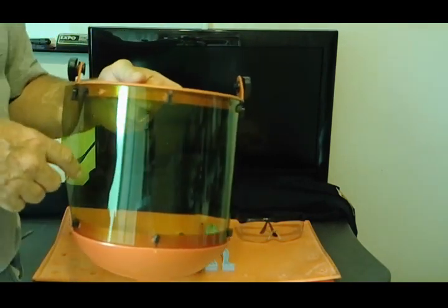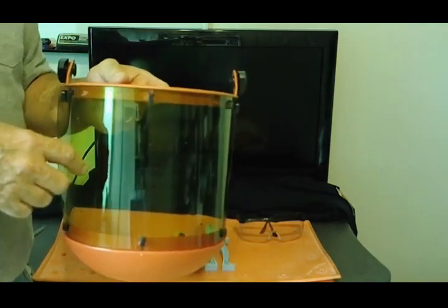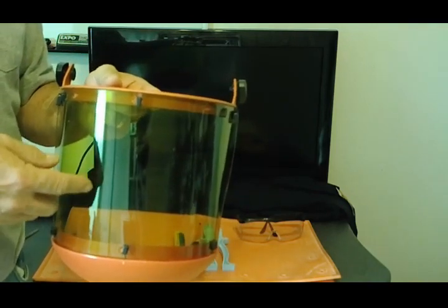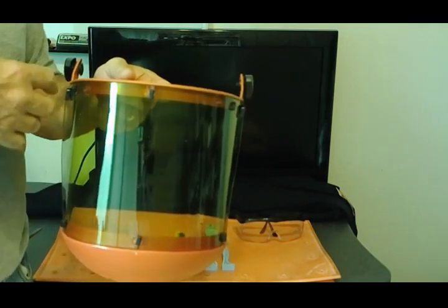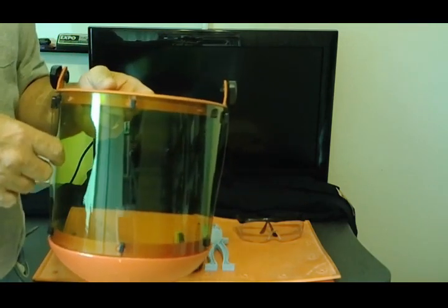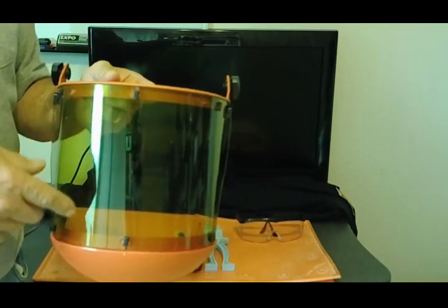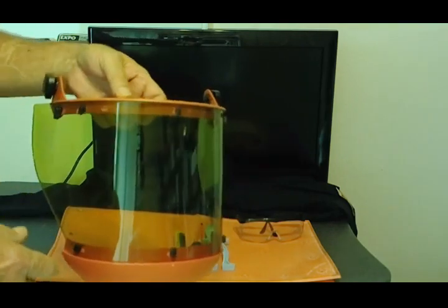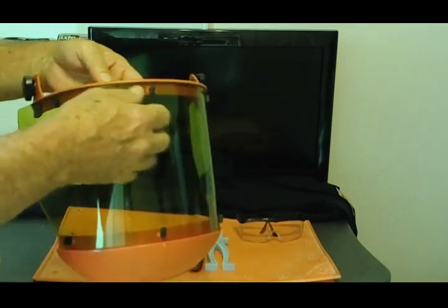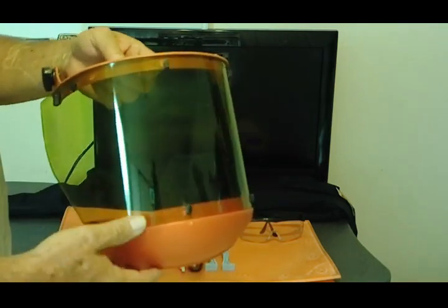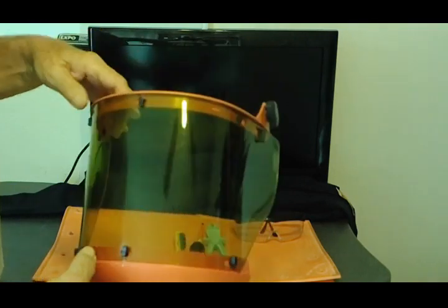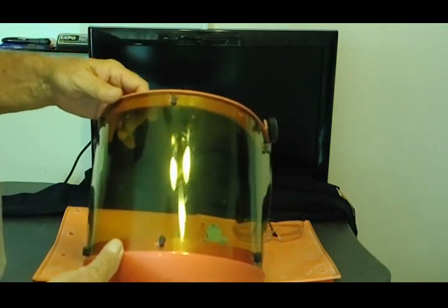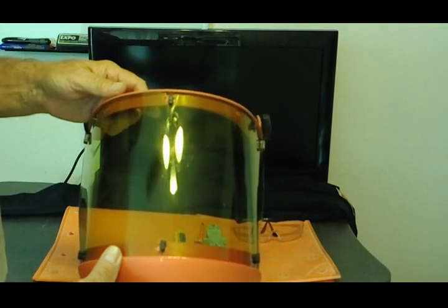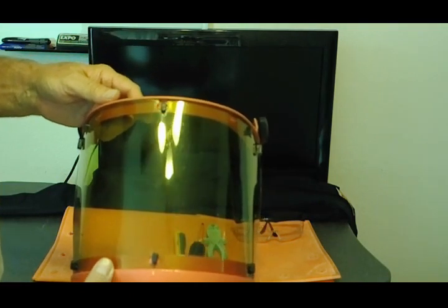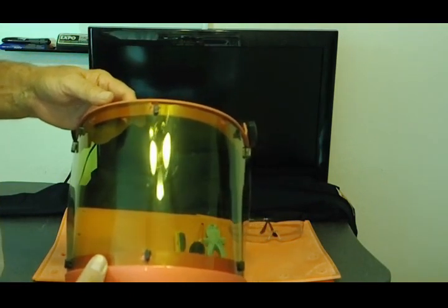Now the yellow tint, it can be a green tint or yellow tint. That yellow or green tint is there to provide UV protection in the event of an arc flash. Now they do make a clear one, but if there's ever an arc flash, you're going to have a real case of welding burn or sunburn right there on your face. So you got the colors. Now once the color's there, this also creates another problem: it makes you colorblind. It's hard to tell the difference between green, blue, and orange. So you really got to pay attention to these.